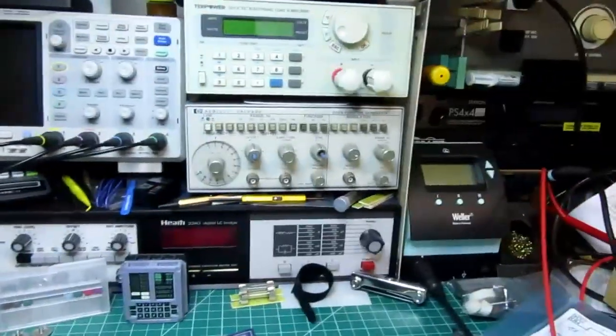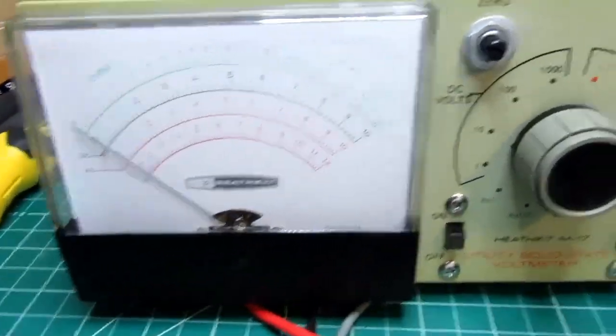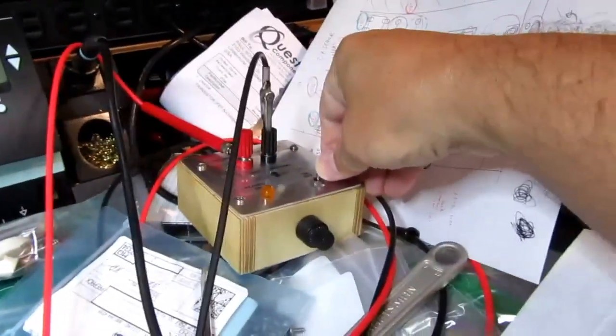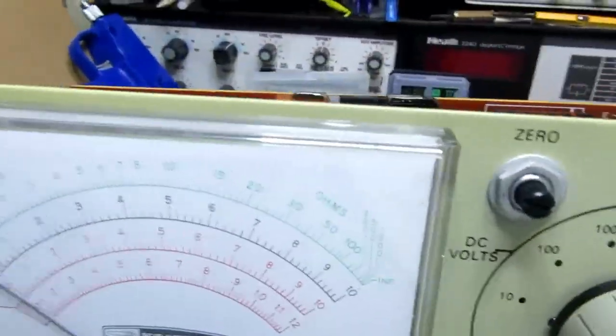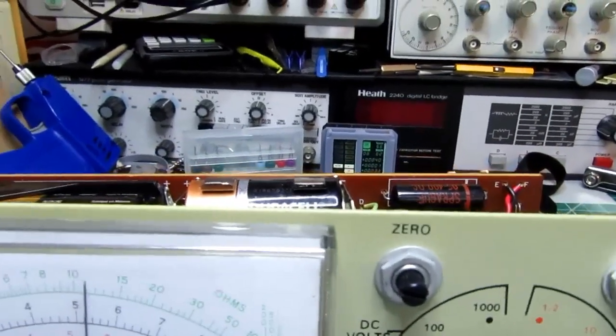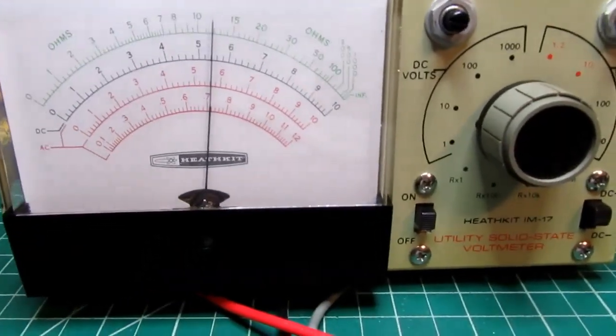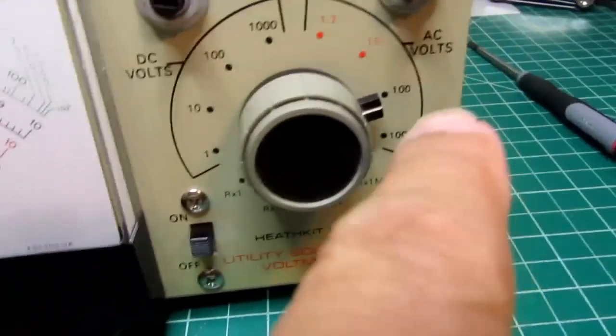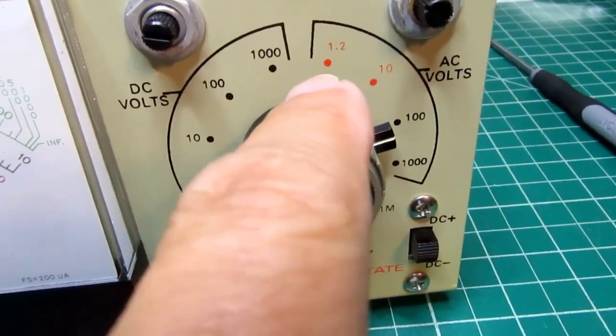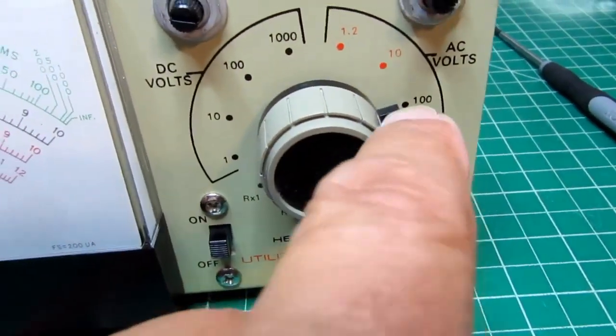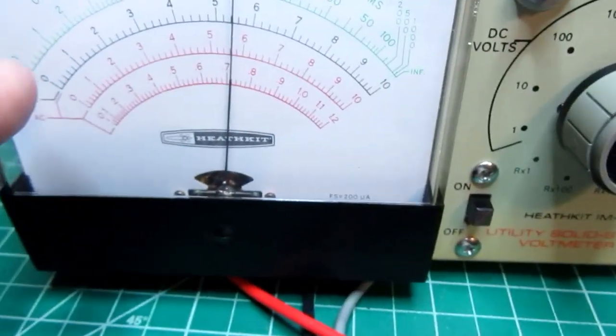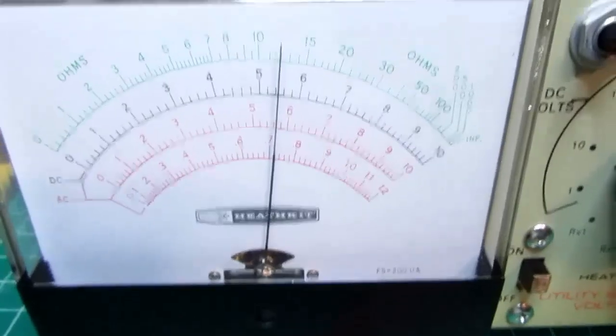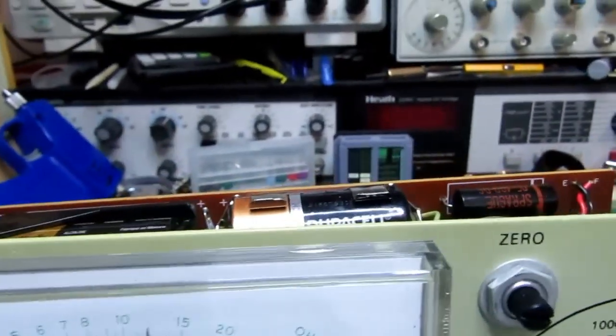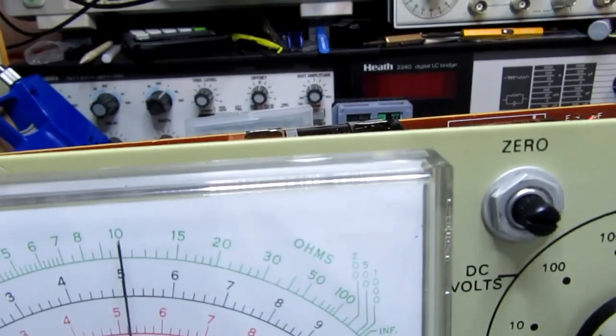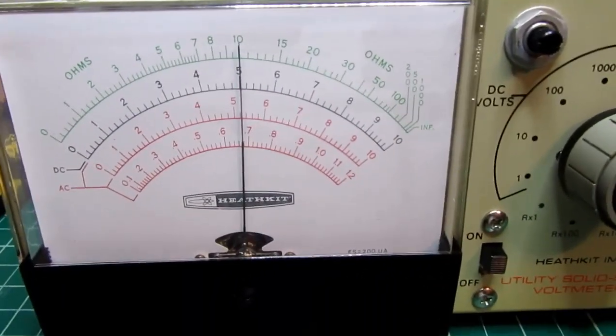And I'll start cranking it up. Oops, I have to turn this switch on too. Okay, so somewhere around 50 volts. And I should be using the black scale. This is color coded. Use the red scales when it's indicated here, and the black scale on the meter when it's indicated. So I should be using this black scale. It's reading a little high. The meter on the Variac's also reading a little high. Yeah, that's more like it. 50 volts.